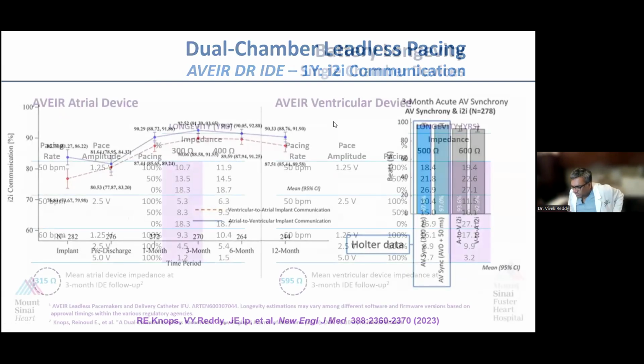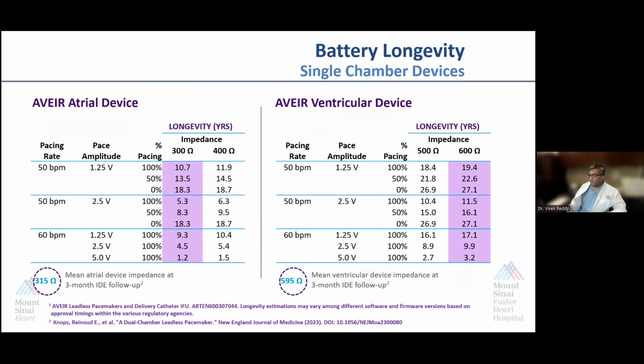I also want to just touch base for a second on battery longevity, because I think this is an important point. If you look at the single-chamber devices, you can see that the battery longevities are quite remarkable. Let's take a look at, for example, just the ventricular device for a second. If you're pacing infrequently, you can have battery longevities that exceed 2 decades, okay? Now, the atrial device is a little bit smaller than the ventricular device. The battery is physically smaller than the ventricular battery. But if it's pacing infrequently, so let's say backup pacing, for example, you can have extremely long battery lives.